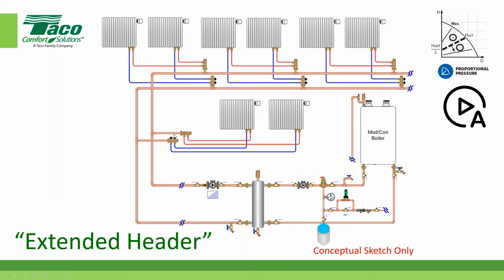You got the mains, you got the branches, you got the twigs, you got the TRVs, you got the panel rads, and this circulator is going to fill every bit of that. So as these panel rads modulate open and close within the system, notice this just keeps going. Then it's going to feel that and it's going to ramp up and ramp back.